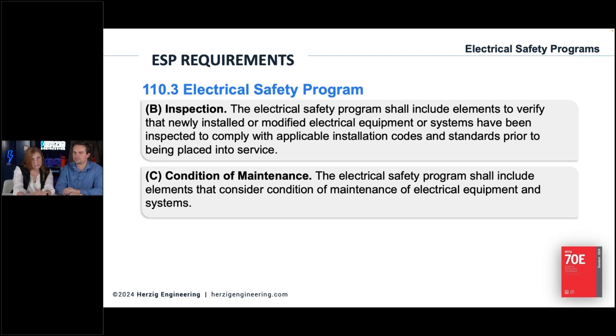It doesn't always happen, but the National Electrical Code has been around a very long time, so people aren't surprised there's a certain way you're supposed to install it. But the condition of maintenance piece, we did a whole webinar about it, and the NFPA 70B is now a standard as of 2023, in case you missed it. Condition of maintenance isn't just a process issue, it's a people issue, it's a safety issue.